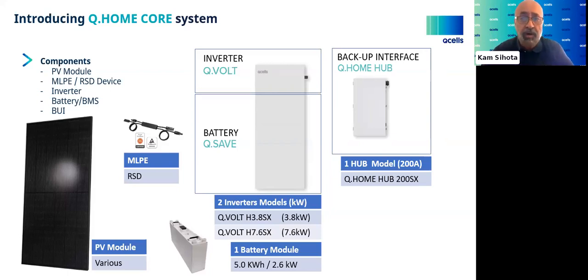We call it the Q.VOLT, and there's a battery right beneath it showing a couple of modules plugged in, called a Q Save. Then the backup interface, or hub, is shown on the right, and that's what brings it all together. We have two flavors of the inverter, a 3.8 and a 7.6 kilowatt, and each battery module is rated at 5 kilowatt hours, with a minimum of 2 battery modules required. So your battery tower could be from 10 kilowatt hours up to 15 or 20. And then 4 of these can parallel into a single hub.